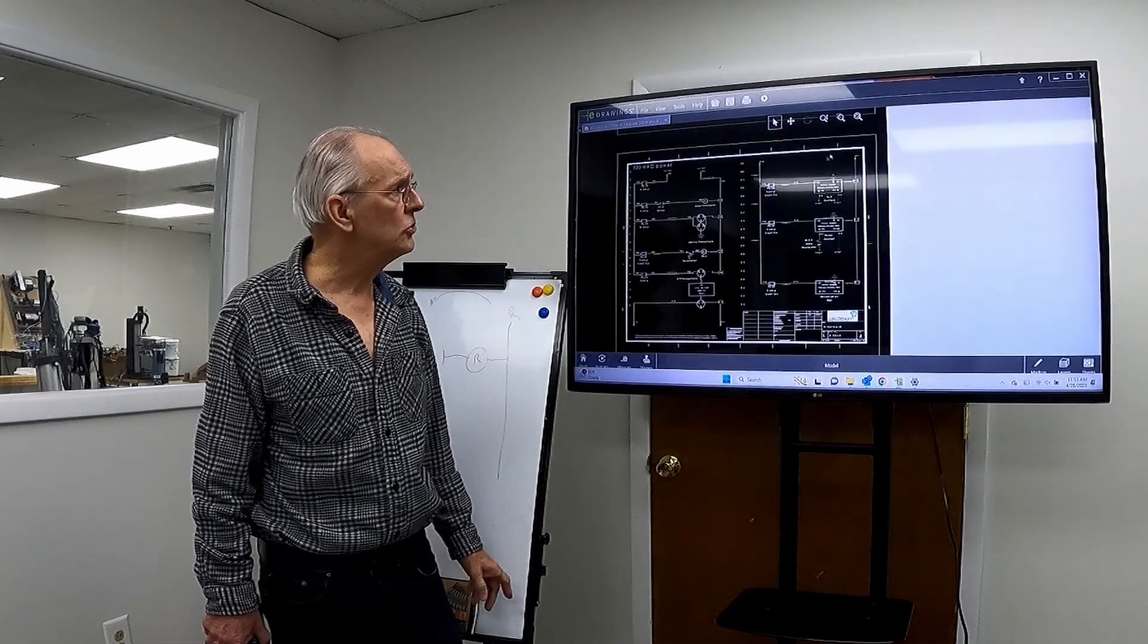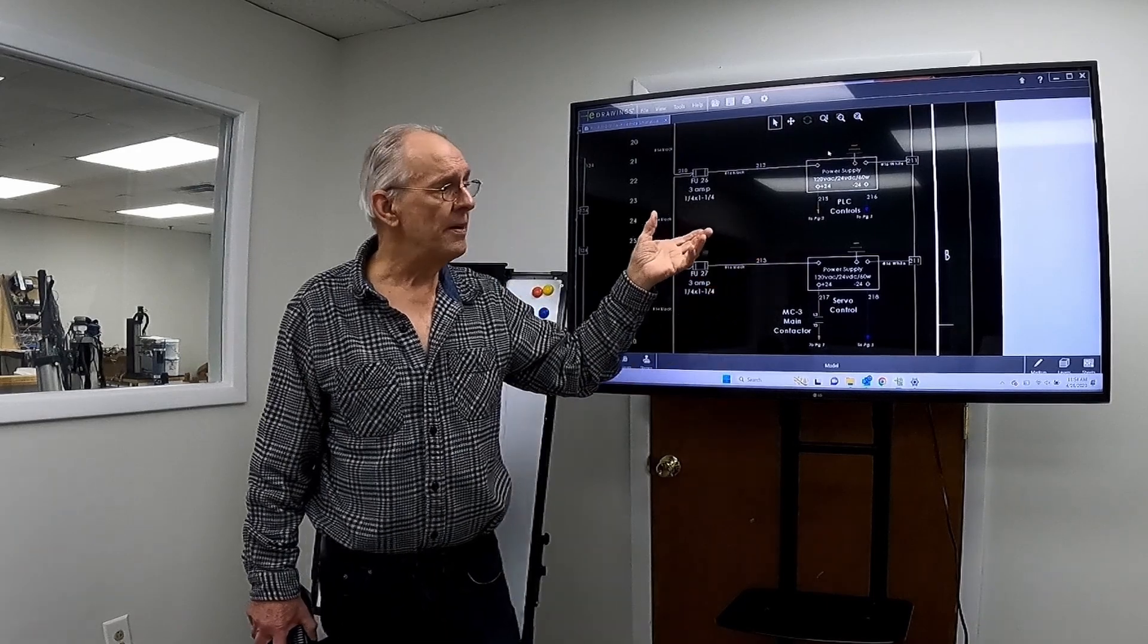So we have two power supplies here, or three actually. One is dedicated to the servo motors because of noise issues. One is the controls for everything else, and then there's one for the HMI itself, because for whatever reason, the HMIs have always been sensitive to power issues. So there's three. These are all DC power supplies. They put out 24 volt DC, but they're used in different places. Now the important thing here is, you'll notice the numbers - you see 215, 216.